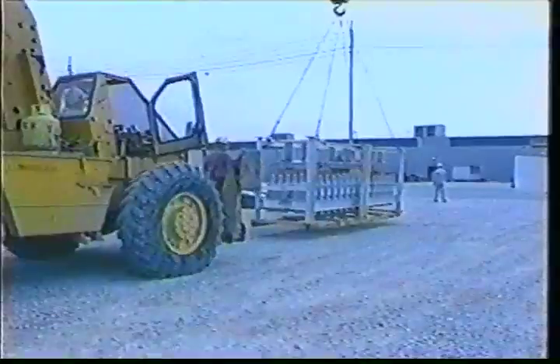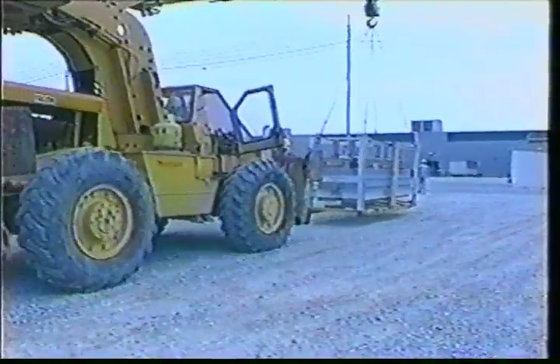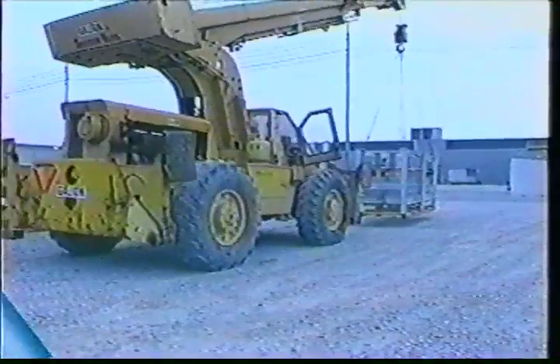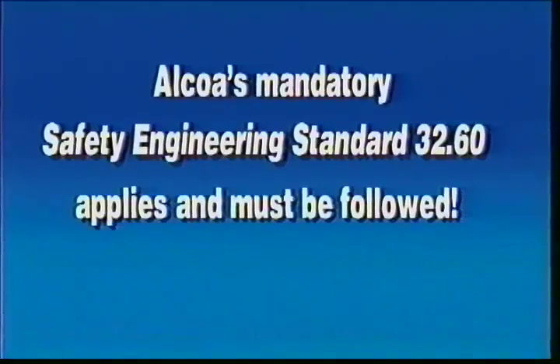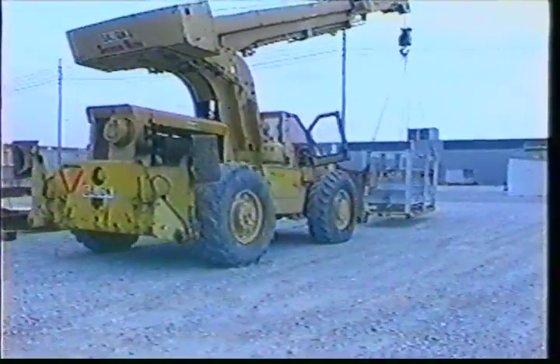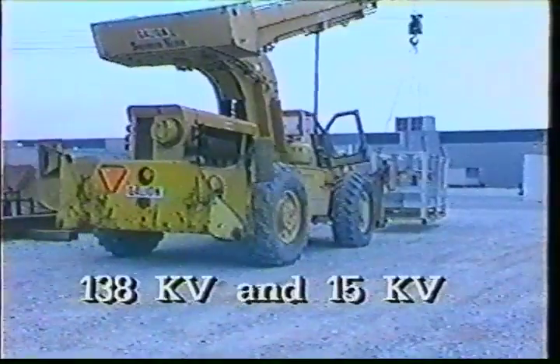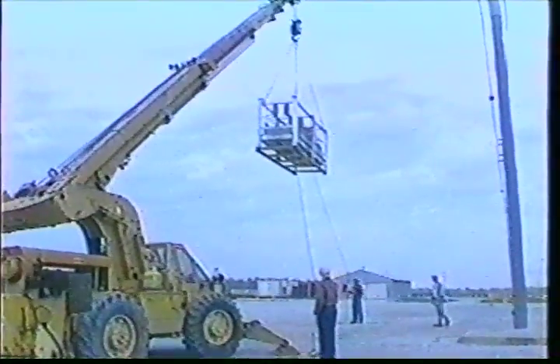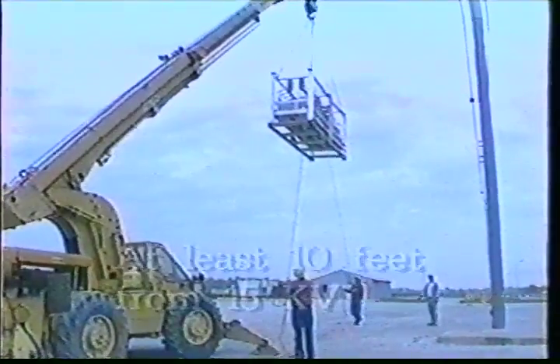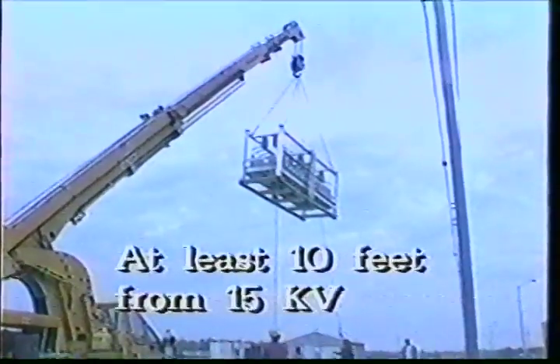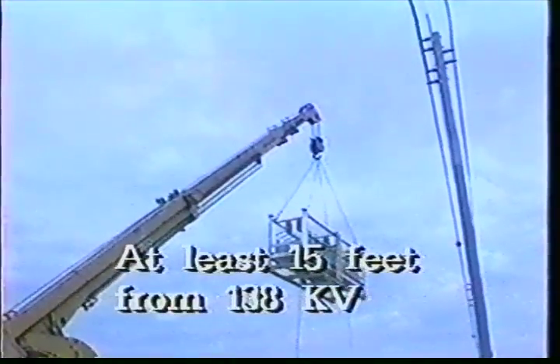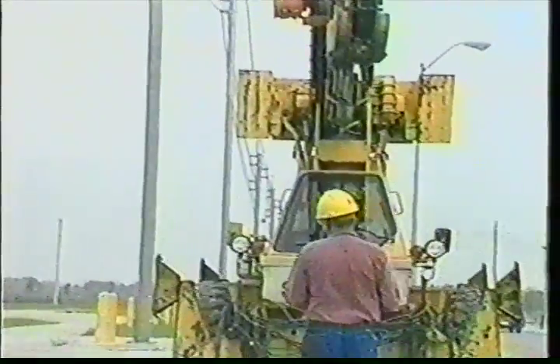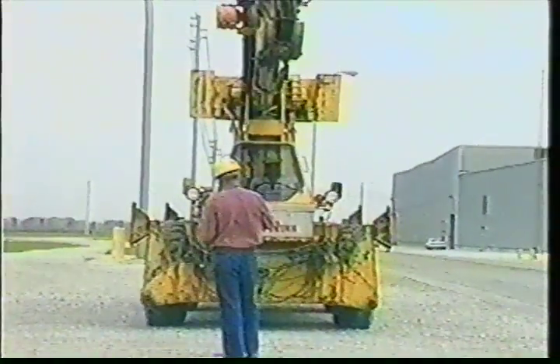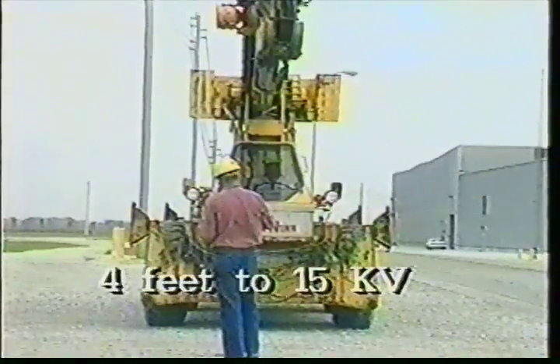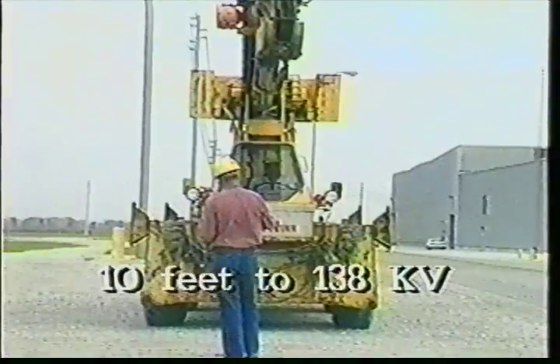the vehicle. For some jobs, it's necessary to operate mobile equipment near energized high-voltage lines and equipment. Alcoa's mandatory safety engineering standard, 32.60, applies and must be followed. At Warrick operations, high-voltage installations are generally 138 kilovolts and 15 kilovolts. When lifting loads near these areas, keep the equipment, lifting cables, and the load at least 10 feet away from 15 kilovolt installations and 15 feet away from 138 kilovolt installations. When in transit, mobile equipment and cranes with no load and boom lowered must not come within 4 feet of 15 kilovolt power sources and no closer than 10 feet to 138 kilovolt sources.